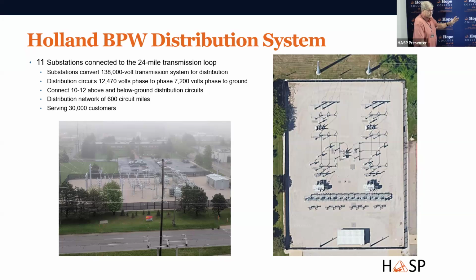Every one of those substations is designed so that no one transformer handles the whole load. There are two transformers, but if one were to go away, the other can supply all the energy coming out - they always have a 50% margin on each transformer, so if one dies, the other one can handle the load. They all look like that.